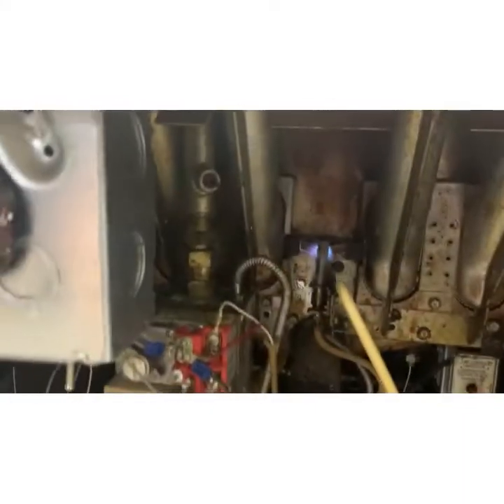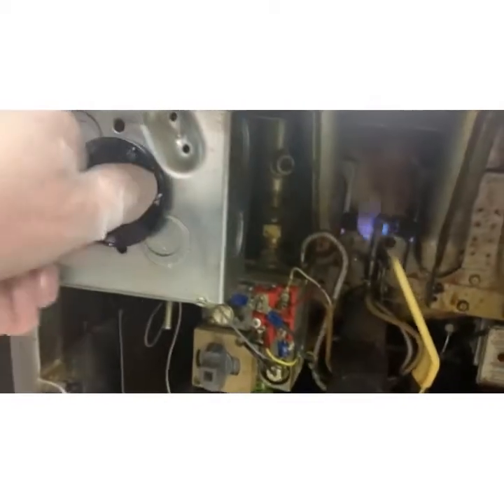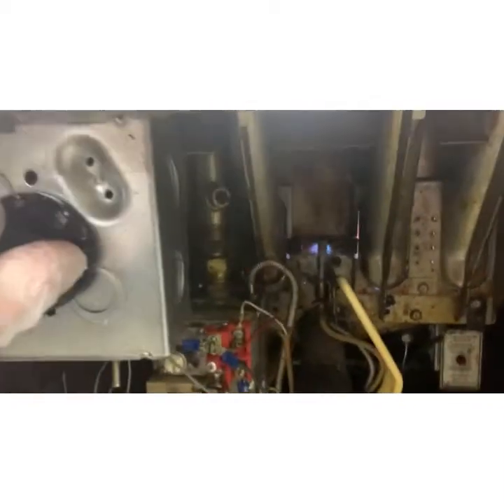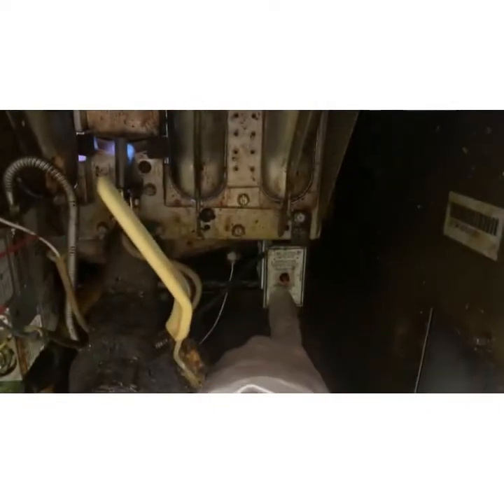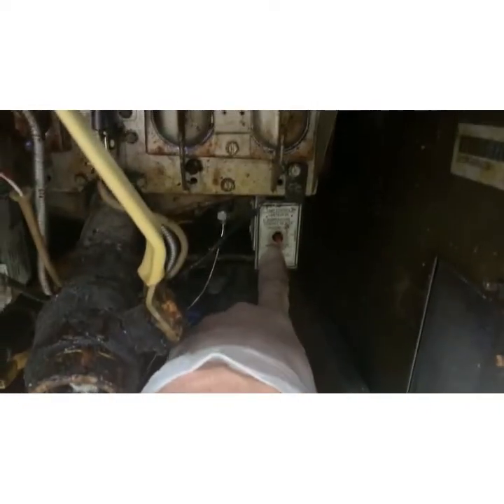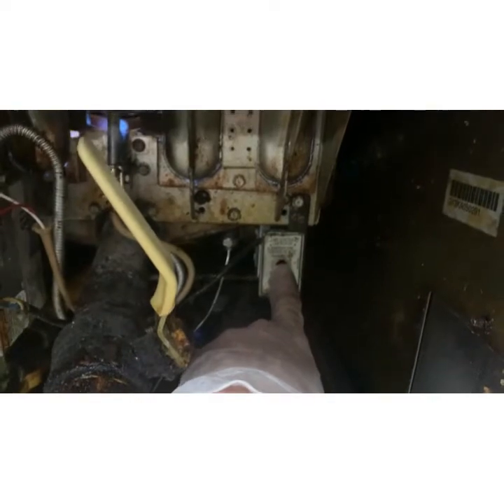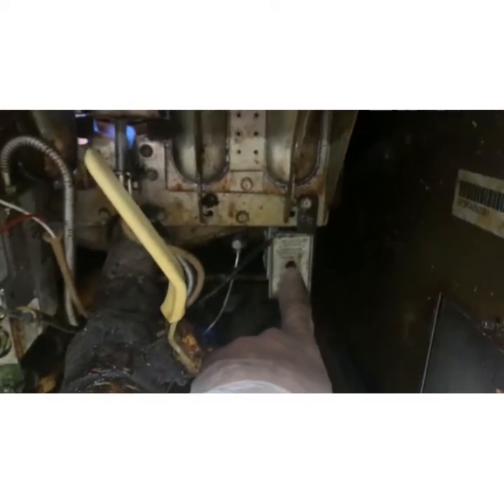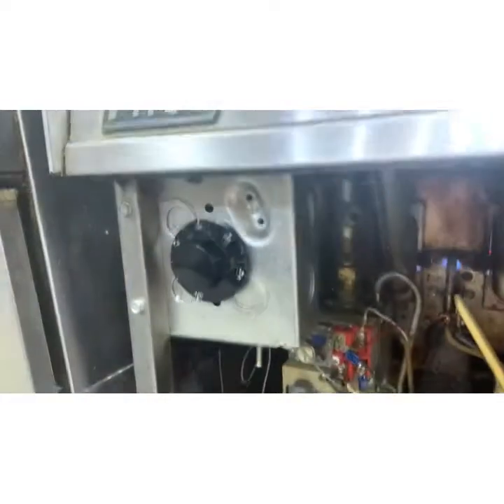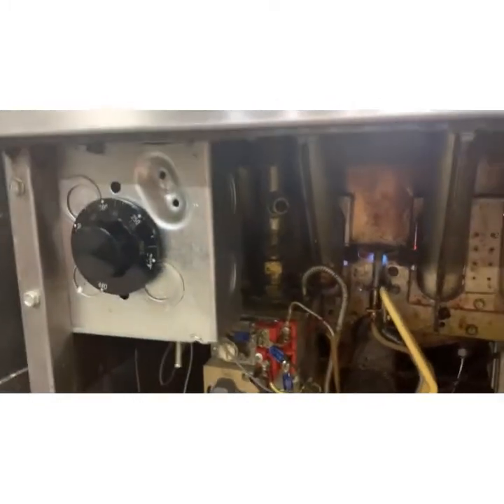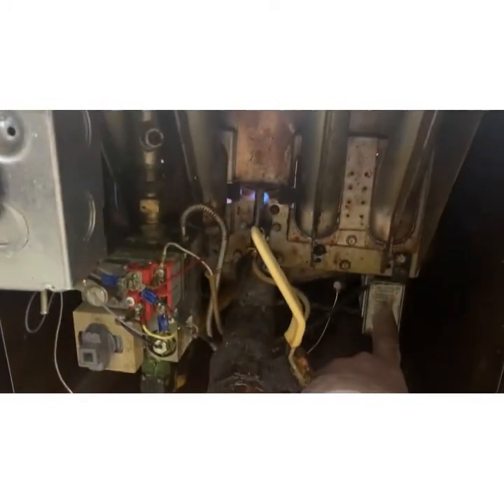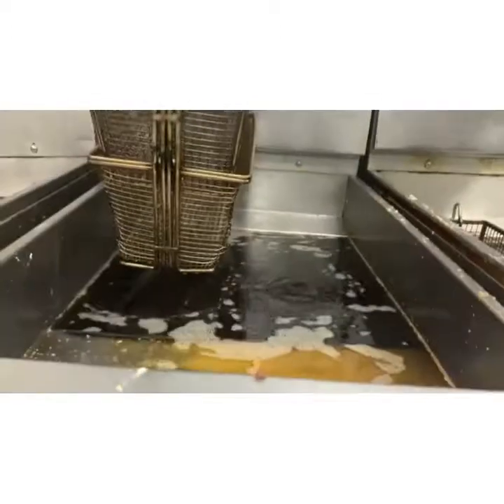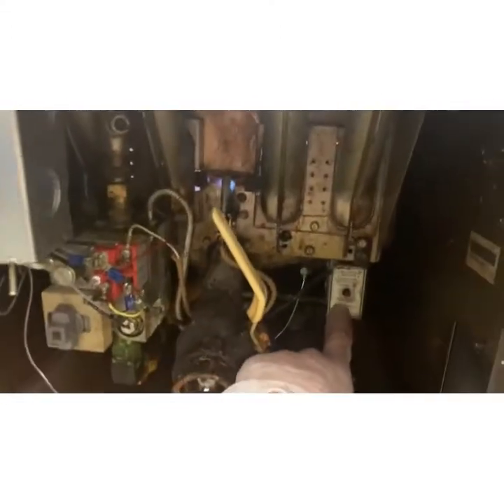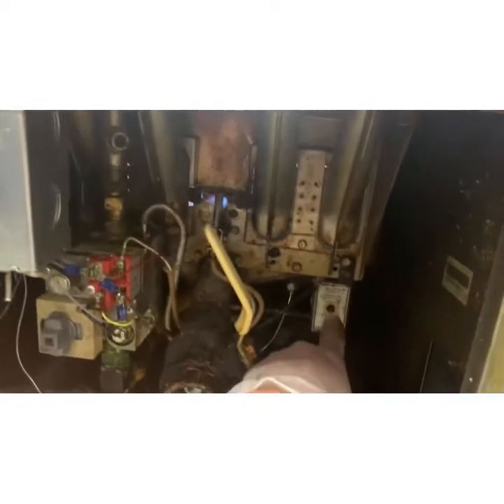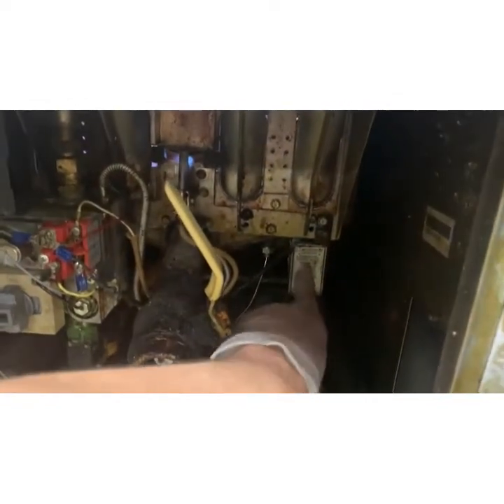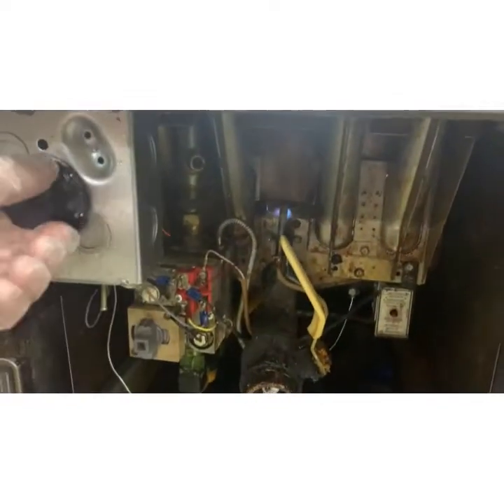But the reason they keep finding it off is that this high limit is set to cut out at about 410 to 420. So in this situation, if the thermostat is running away with nothing to intervene, the oil will get so hot it'll burst into flames. This high limit will intervene, kill the pilot, and you're done.